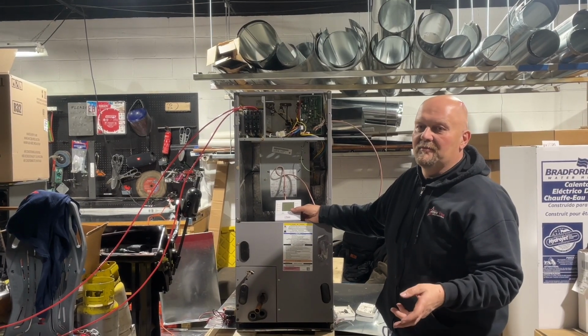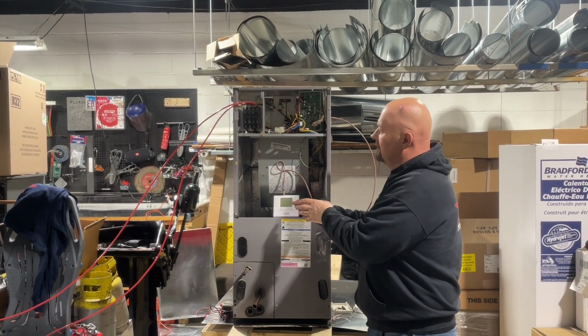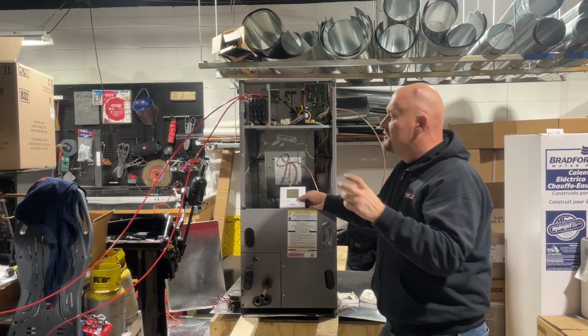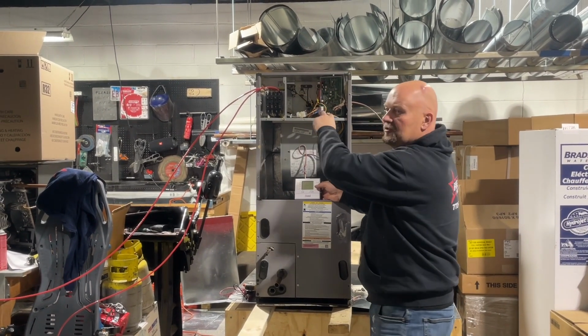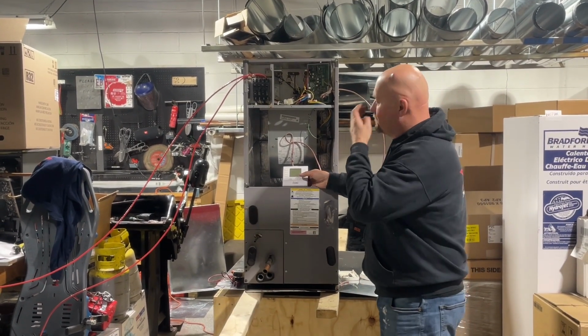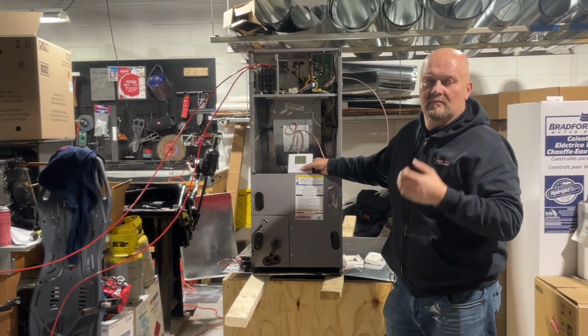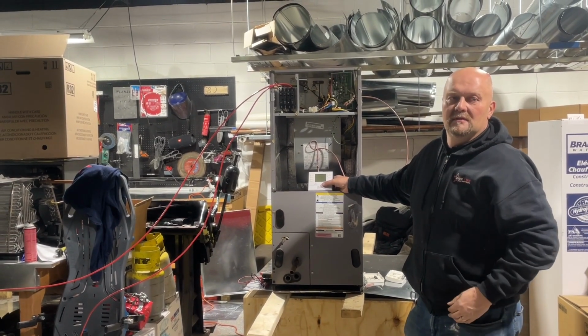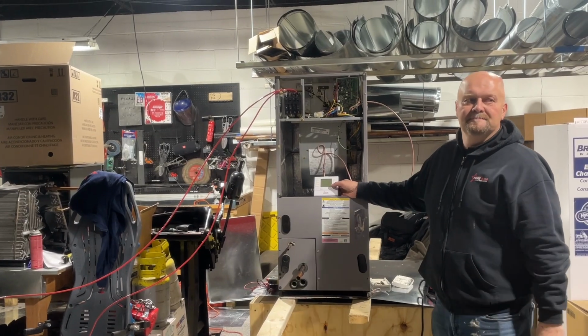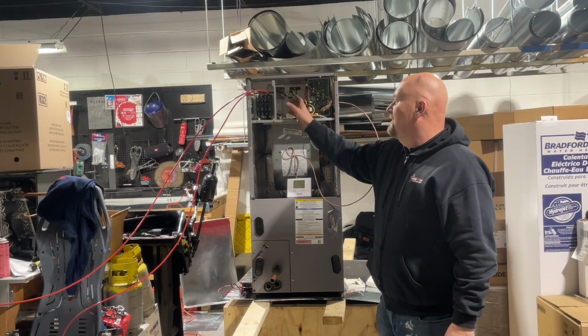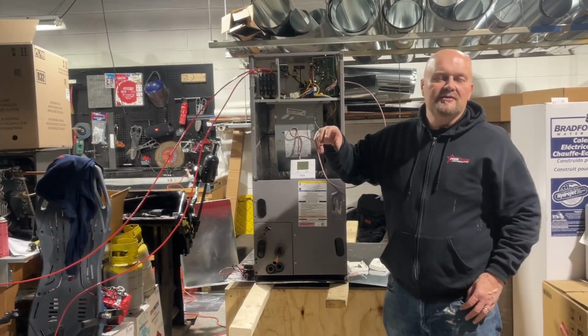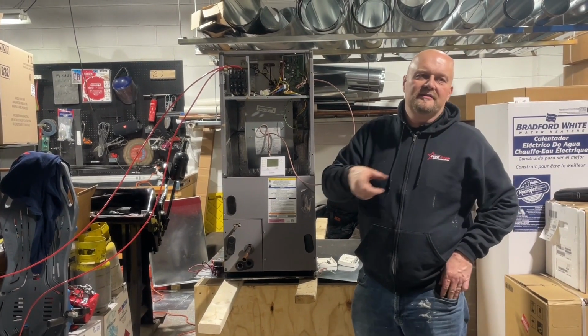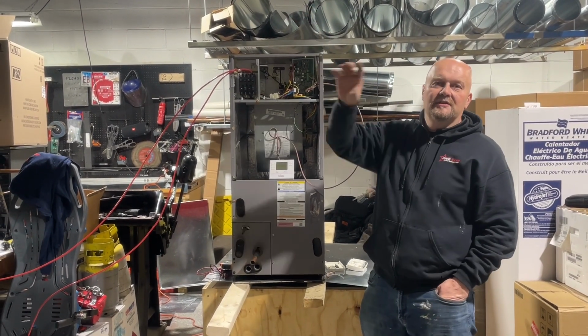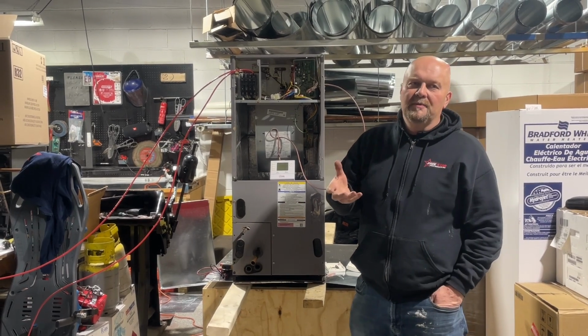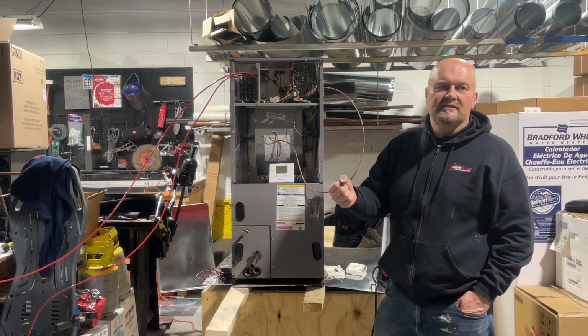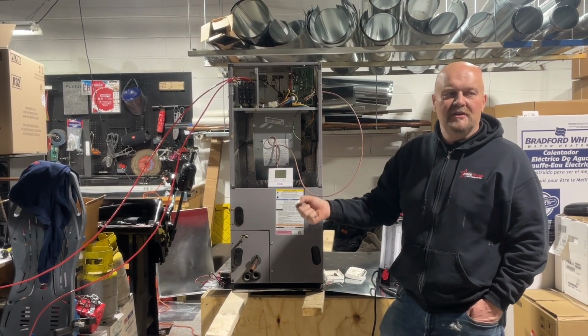So there's not a lot of things happening. Once you have the thermostat calling for heat, you're engaging two relays. Those relays are either external or internal to the control board. For electric heat, usually it's a contactor, just like on a condenser, it just closes the 24 volts, like turning on the condenser outside, except it's on a W. Contactors are loud and chattery, and some of the external electric heaters will literally have contactors. People complain they're loud because they make the chattering sound. You're going to hear that every time your heat comes on.